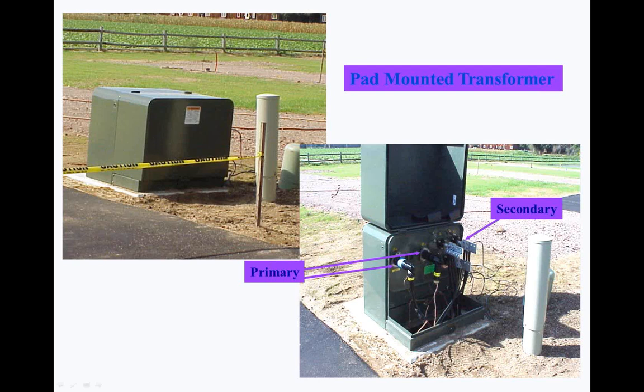And this thing is energized. It has primary coming into this elbow underground, and it originated off of the street where there was probably three phase. It went underground, goes down through a riser, comes up and pops up and goes in right here. It feeds this oil-filled transformer in the back, and there I can get a hot leg and a neutral. So I can feed four houses with 200-amp service off of this one transformer by feeding everything underground. But I got a big neighborhood and more customers, so I have to feed the primary voltage through, and that's this elbow right here. It goes underground, runs down the street, pops up at the next box, and feeds that.